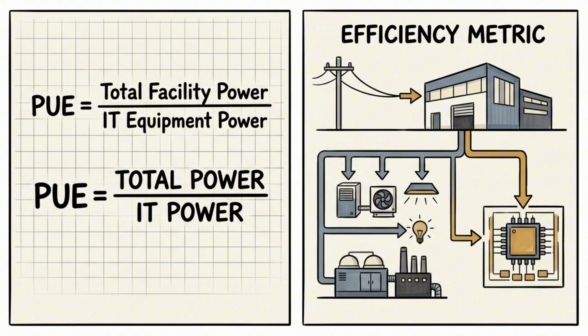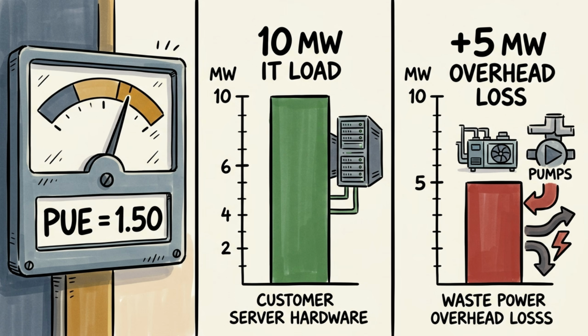Data center efficiency is measured by power usage effectiveness, or PUE, the ratio of total power entering the facility versus power consumed by actual computing hardware. A PUE of 1.5 means that for every 10 megawatts powering customer servers, you burn an additional 5 megawatts just running chillers, pumps, and power distribution losses.